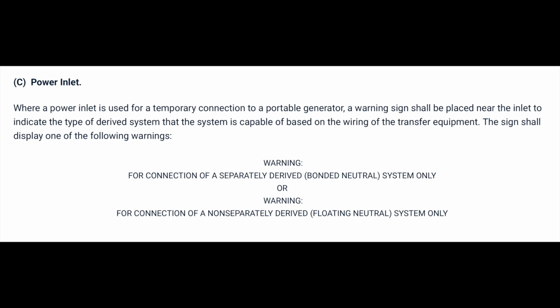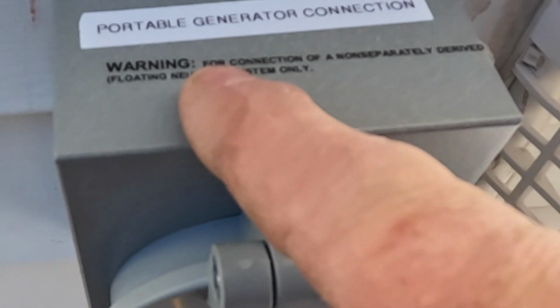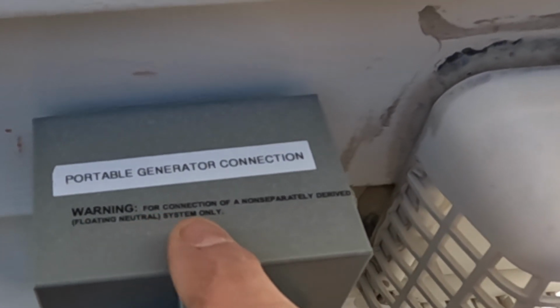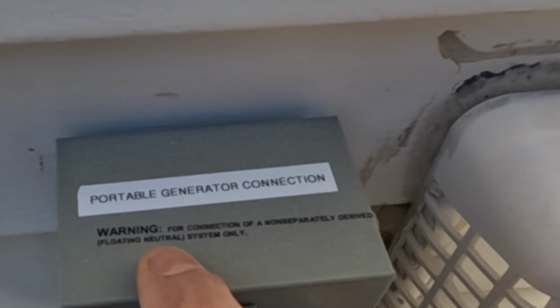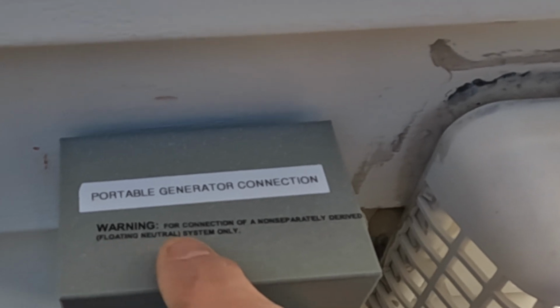In our particular case here, we have a non-separately derived system, and you'll see in a moment here the sticker right on the inlet itself. The transparent sticker here says warning for connection of a non-separately derived system, which is a floating neutral system only. Portable generator connection. It's going to be a nice install. I'm going to start up the generator right now and try it out.